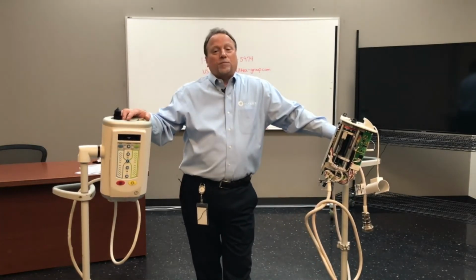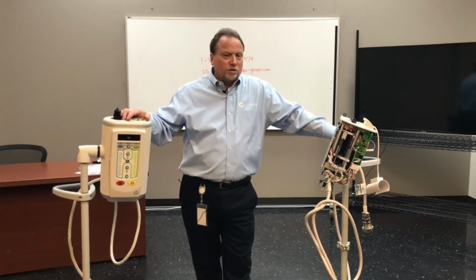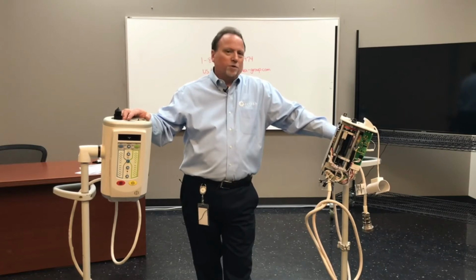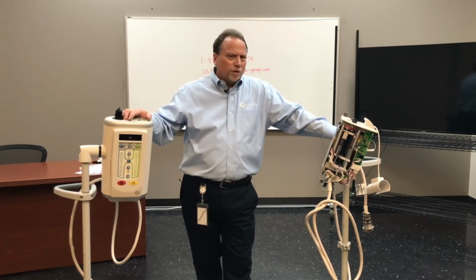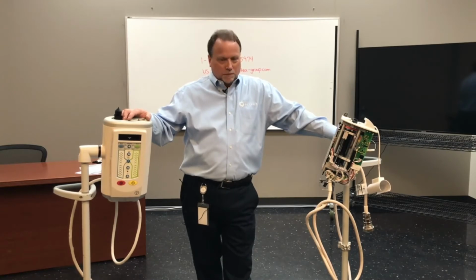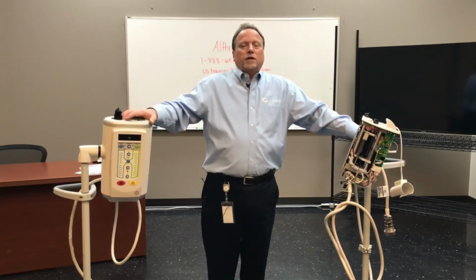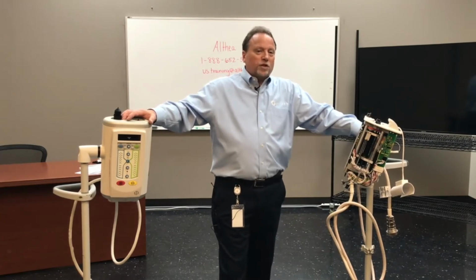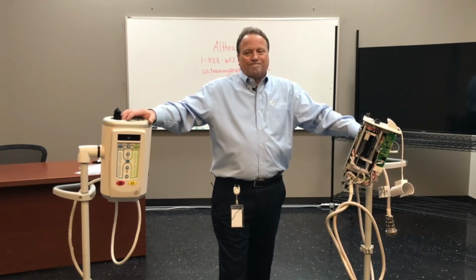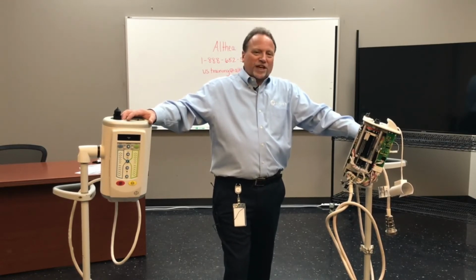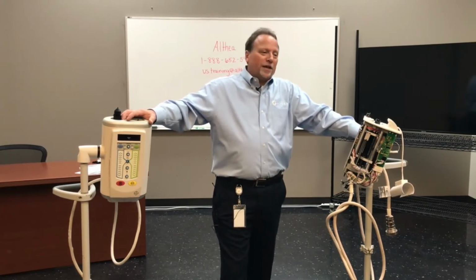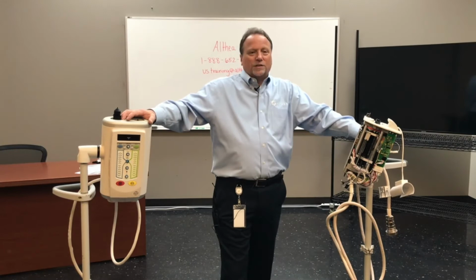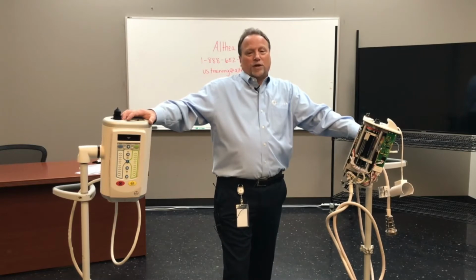One question I get asked quite a bit: do you have the software to do the calibrations on the Bayer systems? No, I've never needed it. What do you mean? Bayer uses it. Yeah, Bayer does use it, and that's fine. Does Bayer calibrate the unit every time they do a PM? No, they verify that it's within specifications and they move on. CTA, Angiomat, Assist, and Certegra injectors actually provide you a way to calibrate those. But with Bayer, they don't give you any information at all.